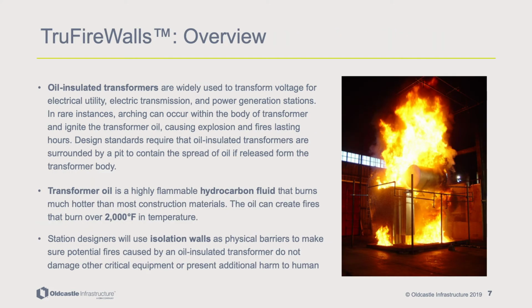Oil-insulated transformers are widely used to transform voltage for electrical utility, electric transmission, and power generation stations. Transformer oil is a highly flammable hydrocarbon fluid used to insulate and cool the transformer that burns much hotter than most construction materials. In rare instances, arcing can occur within the body of a transformer and ignite the transformer oil, leading to explosions and fires. Design standards require that oil-insulated transformers are surrounded by a pit to contain the spread of oil if released from the transformer body to prevent explosions and fires.